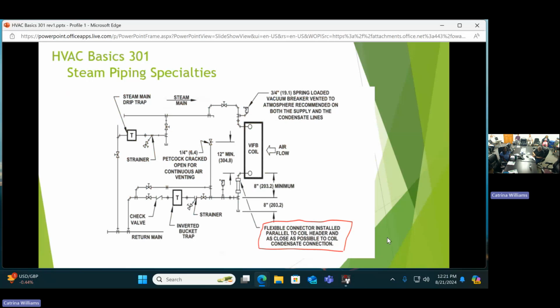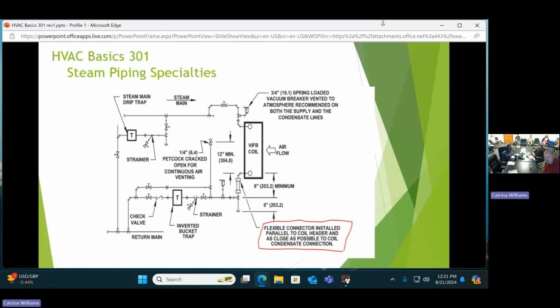Typically you have a trap, and that is to separate steam and condensate, so that just the water can be drained off. The functional trap is not like a two line. No, it's kind of a combination of a check valve and a vent, and does about 3 or 4 different functions. But it's mainly to drain the water off and keep steam. Let me go back to that. Steam can come, depending on the temperature and the heat transfer through the coil, all the way up to this point, to the trap. And we don't want steam going into the water system. We'll stop it there, so that all we should get is water coming down to the condensate line.